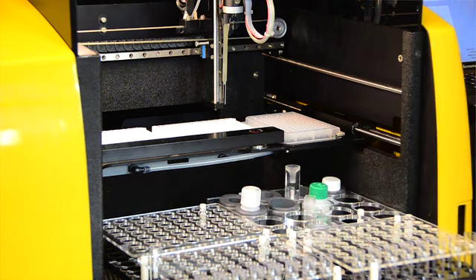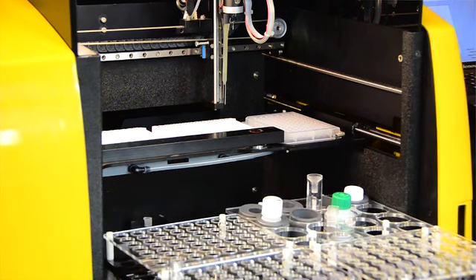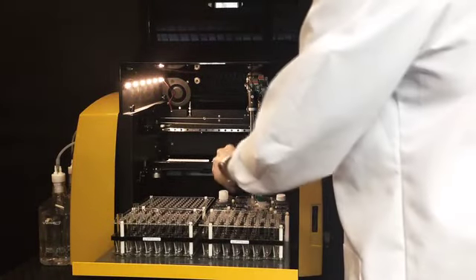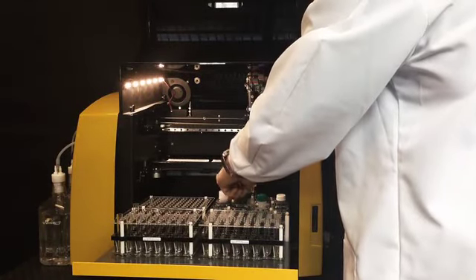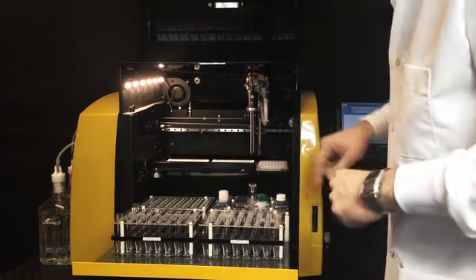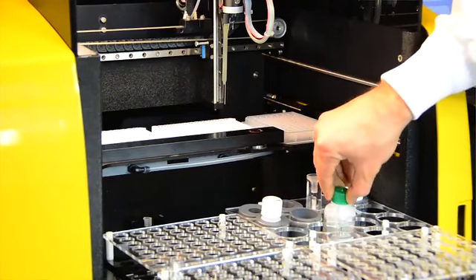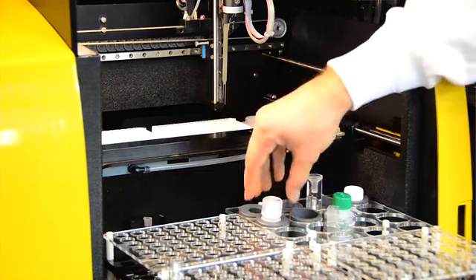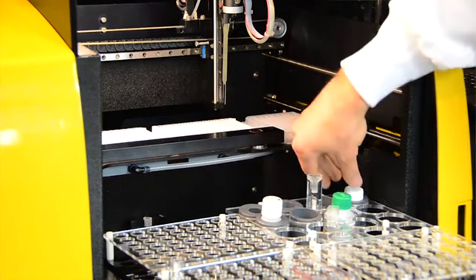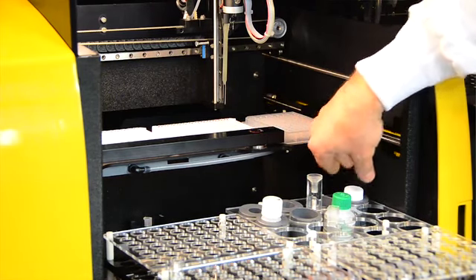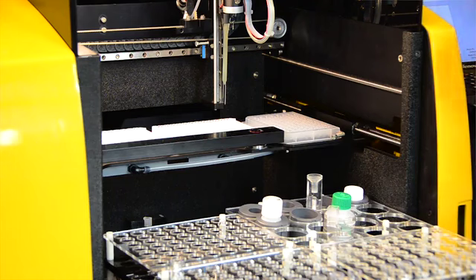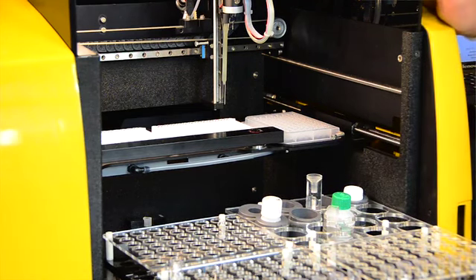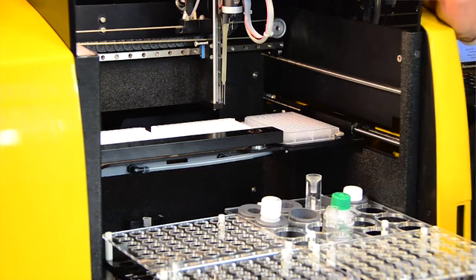In the back here, there are reagent adapters inside of a reagent rack. These reagent adapters are all customizable. We make these so that you can open your kit, take the bottles that come in the kit and put them directly into the instrument. Once again, we're just trying to simplify your experience and not make it any more complicated than it needs to be. If the reagent adapters don't fit the specific size of reagent bottles that you have in your kit, we can actually custom make those as well as the sample racks.